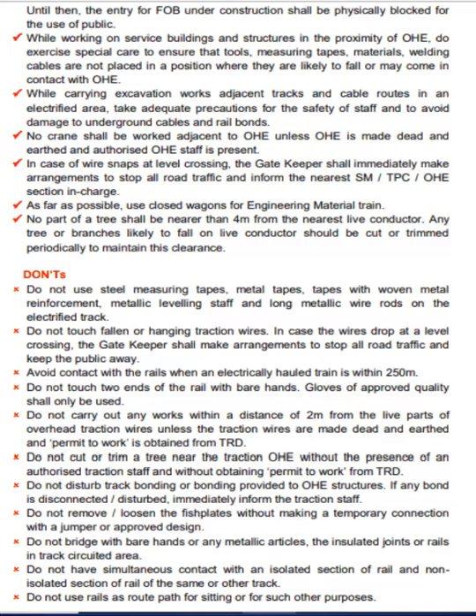No part of a tree shall be nearer than 4 meters from the nearest live conductor. Any tree or branches likely to fall on the live conductor should be cut or trimmed periodically to maintain this clearance.